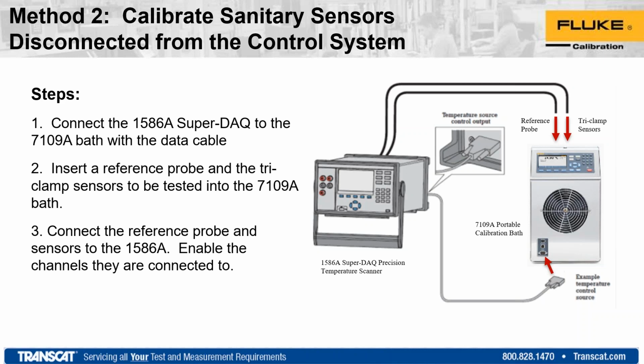So again, this is where we dig into a little more robustness, and you can start digging in pretty hard, depending upon how you're going to analyze the data you're getting from it. In that first example, we were just assuming we were doing a quick calibration, comparing temperature to temperature. With some of these new methods where you're pulling the unit completely out, again, depending upon the controller interface, there may be some potential to input various coefficients to correct for, say, sensor drift, and that could be on the RTD or the control board side of the fence.